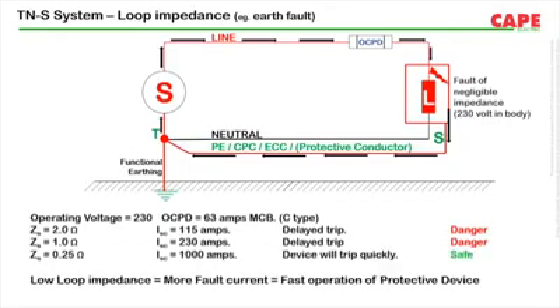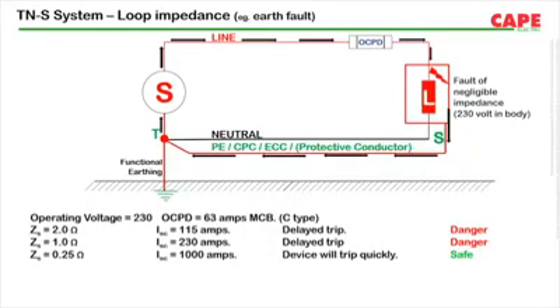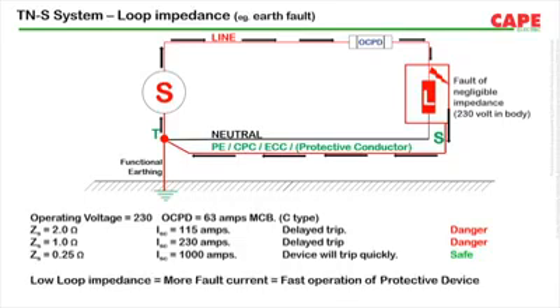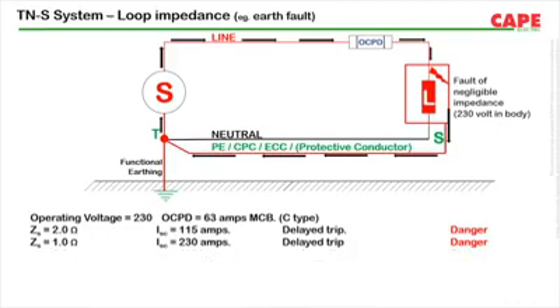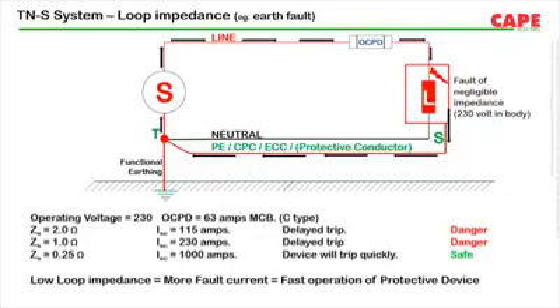A small calculation is shown here for a 63 amps MCB. The desired fault loop impedance of a 63 amps type C MCB is less than 0.36 ohm, approximately 250 to 300 milliohm. The safety principle of automatic disconnection of supply is that low fault loop impedance results in high fault current, of the order of multiples of rated current of the device, resulting in fast disconnection of the supply.